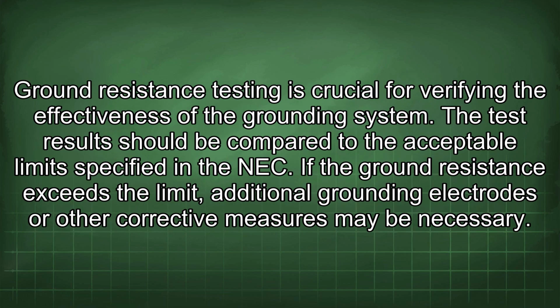Ground resistance testing is crucial for verifying the effectiveness of the grounding system. Test results should be compared to the acceptable limits specified in the NEC. If the ground resistance exceeds the limit, additional grounding electrodes or other corrective measures may be necessary.